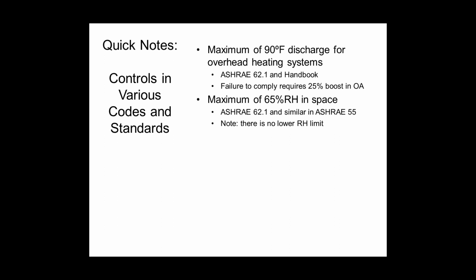Babysit the relative humidity in the space. ASHRAE 62.1 requires a maximum of 65% relative humidity in the space. You're not allowed to go higher than that. I typically recommend controls guys maintain it below 60 and alarm it at 65. ASHRAE 55 does not give you a specific defined number. It gives you the comfort graphical method. But generally speaking, if you keep that 65% number in mind, the graphical method will usually fall in line with that also. So control it to 60, alarm it at 65.